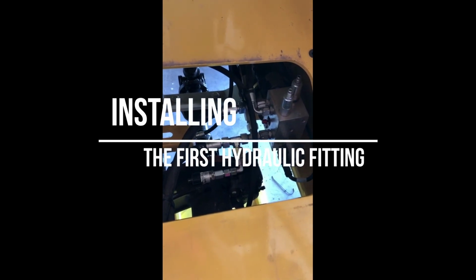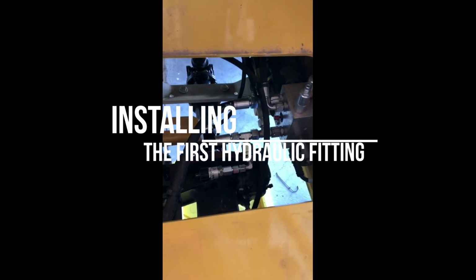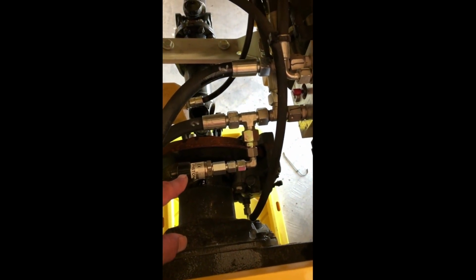Okay, I've traced my hydraulic lines down to a spot where I can install a T. I've installed the piston side one already, and you can see this is where the rod one will go. So I'll break this connection here and install the T. We don't ever want to put the pressure transducers right out at the actual cylinder, because they'll be exposed to more potential danger and damage, and also they'll be moving up and down all the time with the piston or with the cylinder as the bucket moves up and down.